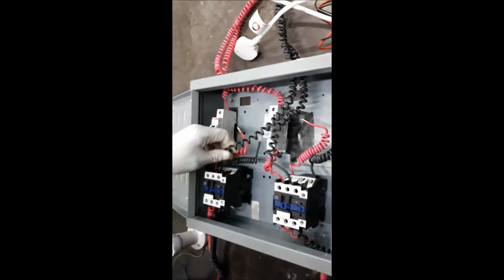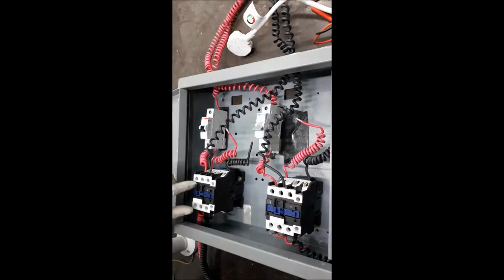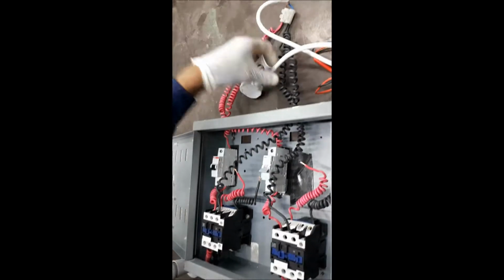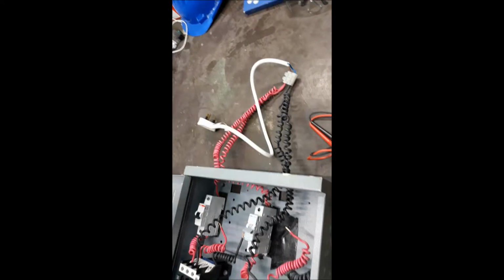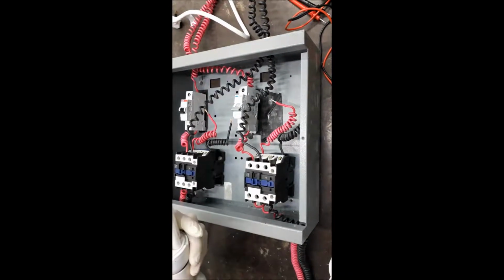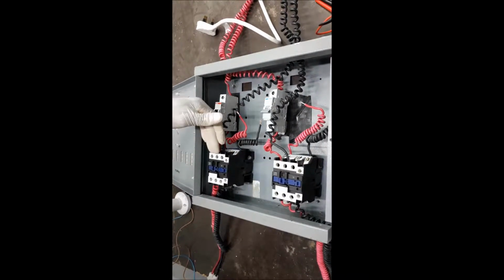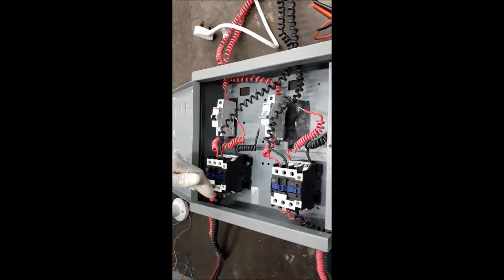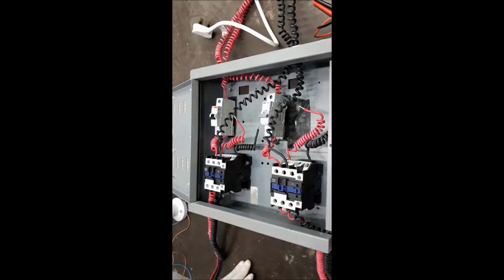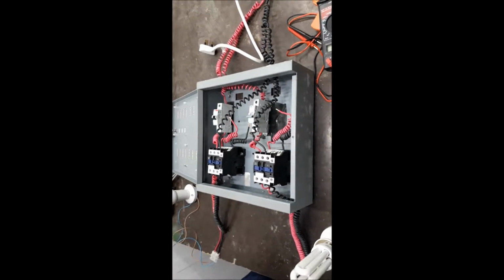I have done a direct alternating current, single phase connection for the motor. For the load, from the power supply source we have a single phase source for the first contactor, and to the load. This is because I have a single phase load. If you have a three-phase load, you are allowed to connect three-phase power supply to the contactor and three-phase from the output of the contactor to the load. If you have a three-phase machine, electric motors, you wish to run and switch over each time, this is what you have to do.